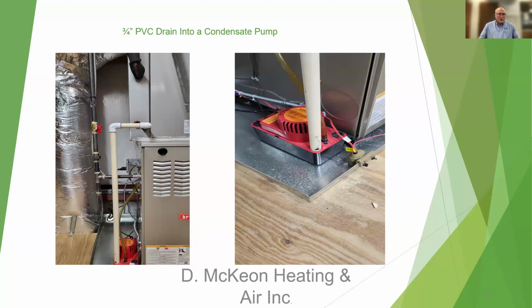Now these are photos and examples of where your pipe comes out of your evaporator coil and where it goes down into a condensate pump. In the pump, we usually put algae pills in there. If you don't have algae pills, you can put Clorox in that pump. Just be careful you don't splash it all over the place, but put the Clorox in it, and that will kill any mold, spores, and that kind of thing that would be in there.